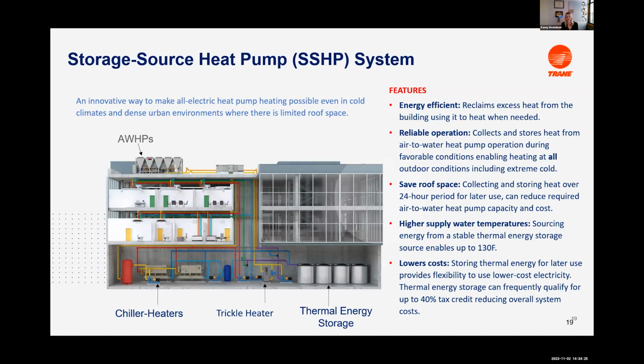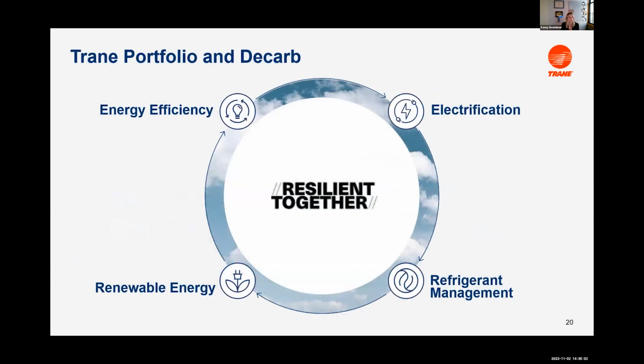On top of that, I was also going to mention our cascading chiller system, which is engineered to order, where we are using centrifugal chillers to get to these really high temperatures, because your heat pumps are often limited by the lift that is available on those units. It allows us to bring colder water to hotter temperatures, which is a big gap right now in electrified heating systems. I don't have too much detail on that because, as Colin said, it's very new, but it is a really exciting system that we are doing quite a few designs on and looking forward. People are very excited about it.